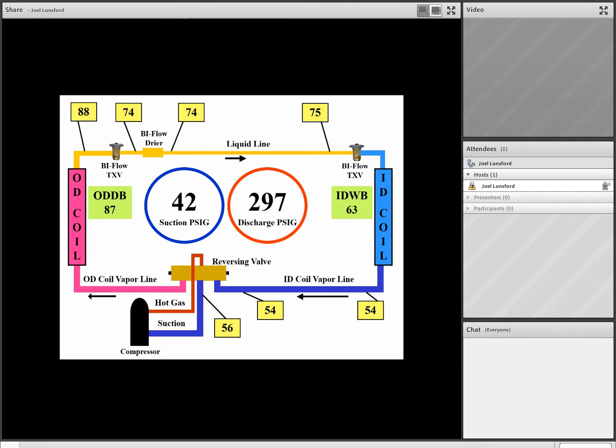Now remember, team, the biflow TXV has a check valve in it that's supposed to allow liquid to flow freely in the particular mode of operation that it's in. So in this example, the outdoor TXV should be flowing freely in the cooling mode and metering refrigerant into the outdoor coil in the heating mode. Likewise, the biflow TXV on the indoor coil should meter refrigerant into the indoor coil in the cooling mode, but flow freely through its check valve circuit in the heating mode. Well, we see that the biflow TXV outside, which should be flowing freely in the cooling mode, has got a 14 degree temperature difference across that biflow TXV check valve circuit.